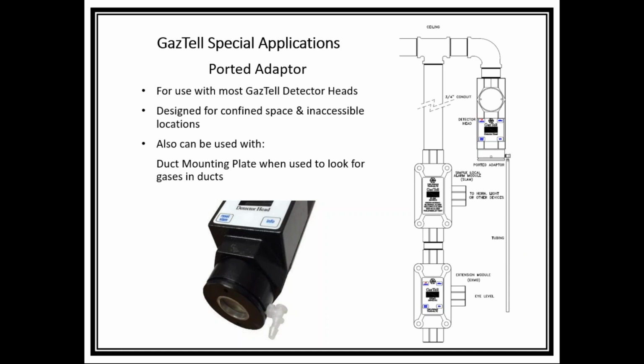It could be used in confined space areas. We've seen it used in elevator shafts. Some applications are in hotels. We've used it in stairwells where the stairwells were so high that the technician couldn't easily get to that detector head to calibrate. So it's a very popular option.